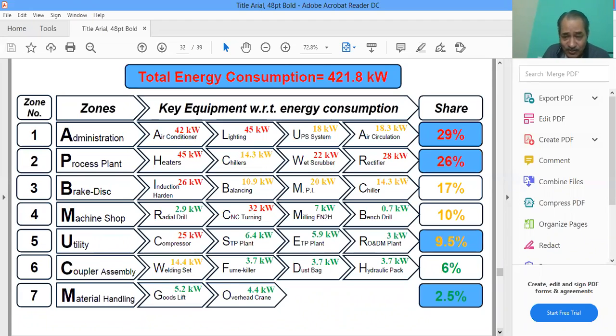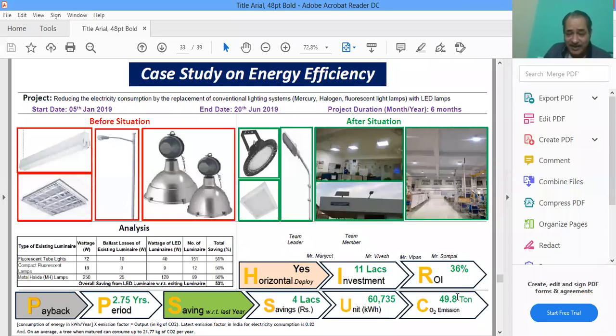When you analyze this in depth, you'll see in the slide that the fluorescent tube lights had a wattage of around 72 watts, plus ballast losses of around 10 watts, so total consumption was around 82 watts. Whereas with LED, through the luminaries, the wattage used is 40 watts, meaning approximately 50% savings. Multiply that by the number of luminaries, 151, and the savings get multiplied further.